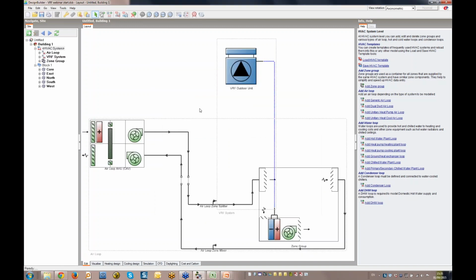We'll now use the VRF with heat recovery and DOAS template to explain some of the key concepts associated with VRF modelling in DesignBuilder. The schematic of the VRF system shows it simply as the outdoor unit connected via refrigerant pipework to the indoor unit. This can be used to model a standard two-pipe system or a refrigerant heat recovery system. Jim will talk more about the finer points of successful heat recovery installations during his session.